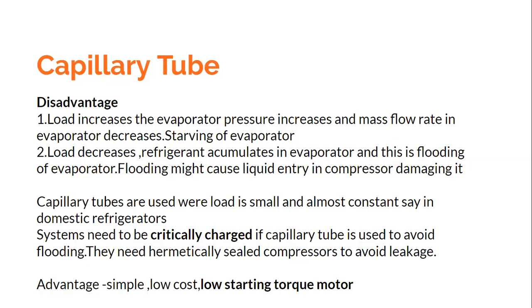Now, flooding is more dangerous because when there is a flooding of refrigerant in the evaporator, the liquid refrigerant would enter the compressor, and when it enters the compressor, it might damage the compressor. So flooding has to be avoided. Now, how is this avoided? Because that is the disadvantage of the capillary tube. What are the disadvantages?